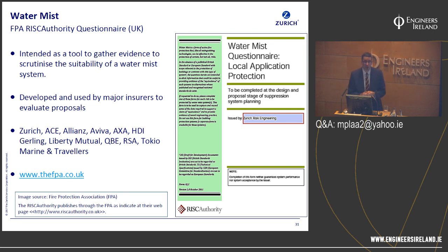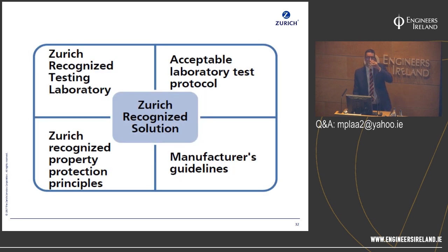I use them a lot because it asks the installer to give you information about the components, about the design, about the calculations, about the pipe sizes, about the fire test protocols. So in order to fully evaluate water mist systems and all forms of fire protection system, Zurich has this 4-stage simple approach. And it's a tool I use that I think you could also use to properly evaluate water mist systems. And what it does is it asks you to go through 4 simple steps.